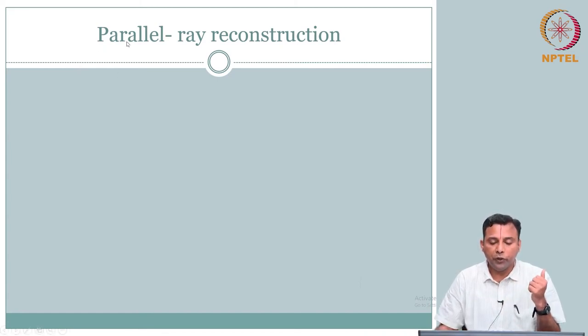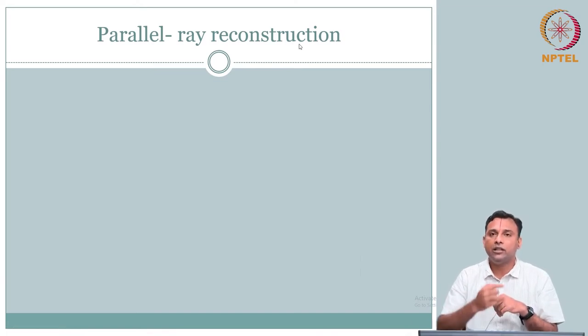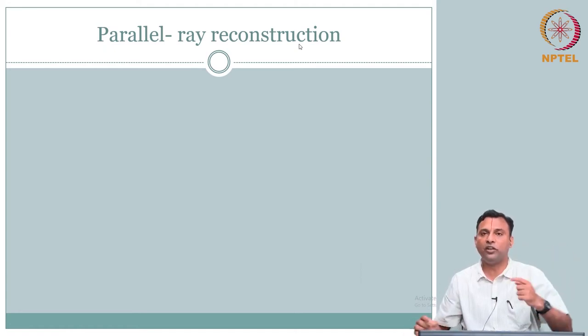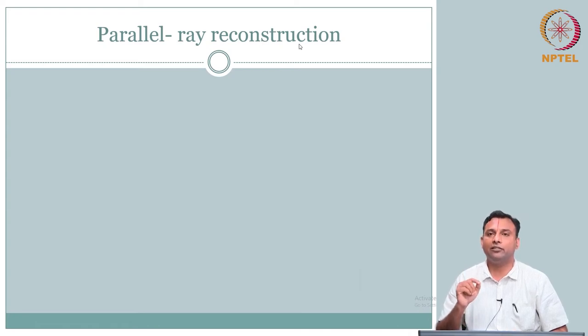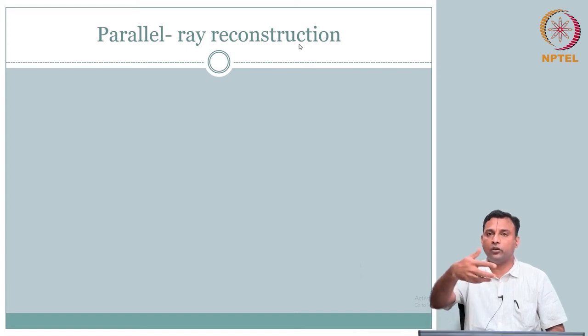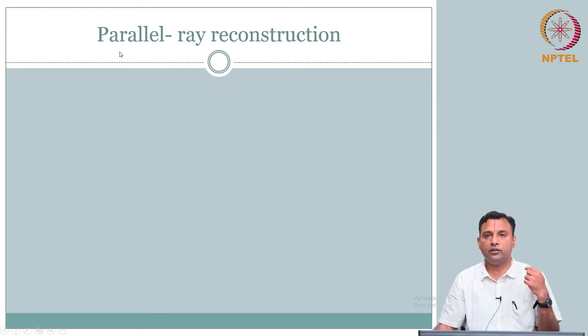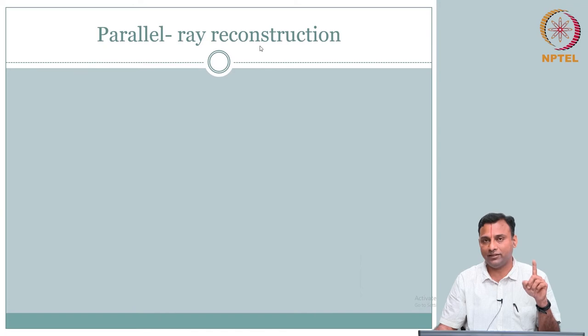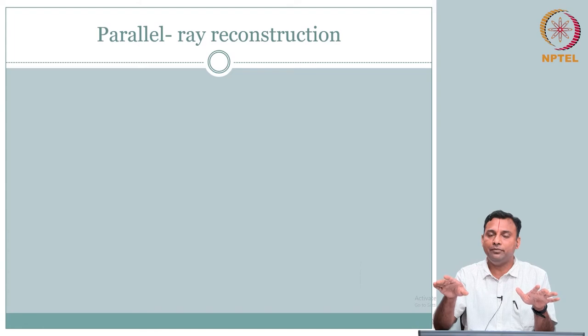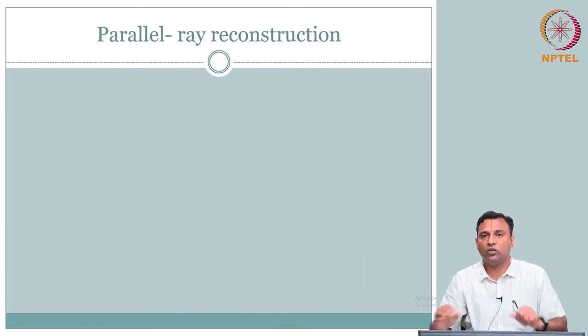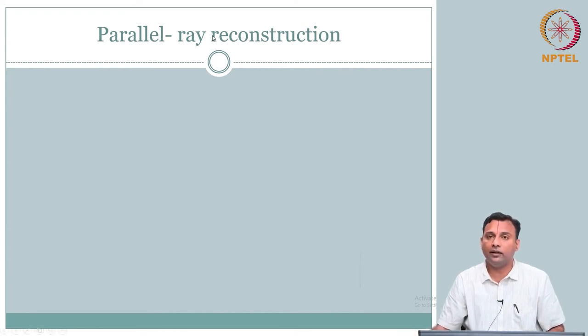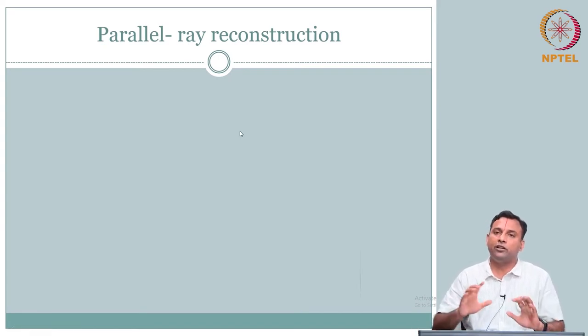Let us get into the reconstruction itself. Just to reiterate, we are going to do parallel ray reconstruction. What is parallel ray reconstruction? We send one x-ray, I have one detector, one line integral. We are going to mimic first generation CT where you translate, send, receive, translate, send, receive - you have parallel lines. We are going to start with simple parallel ray reconstruction, pencil beam, as was used in first generation. After we do this completely, we can expand to fan beam, then to cone beam.